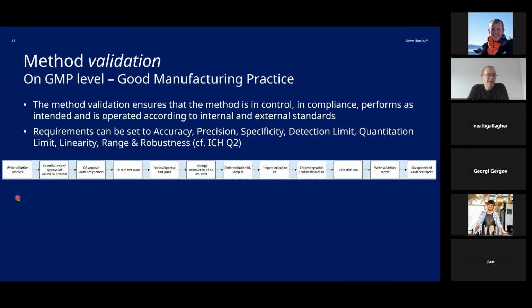We need to take into consideration instrument robustness, method robustness, variation in the matrix, and all these things. So we really would like to see, we want to measure these 40 or 80 or 200 samples with this variation, with these changes in temperature and pressure, and with these small deviations in instruments to make sure that the instrument is robust.